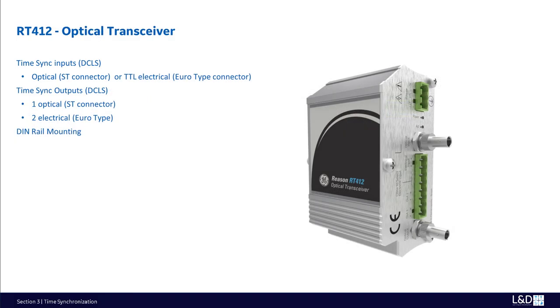The RT412 optical transceiver is an electrical-optical or optical-electrical time synchronization format converter whose characteristics allow multiplication of GPS clock outputs and distribution of time synchronization across the substation where there are significant distances between the panels. It converts a twisted pair electrical input to ST optical fiber output, or conversely, converts an optical input to an electrical output. It has one optical input or TTL electrical input, one optical output and 2 electrical outputs. DIN rail mounting, same as RT431.